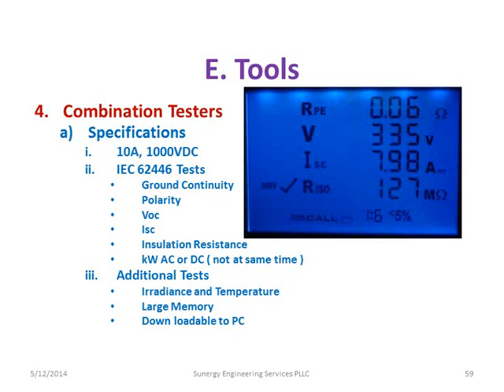So you can see in this is actually the unit right here, and what it looks like when it's live. RPE is the protective earth. That's what they call it in Europe. It's the resistance of protective earth, and it says what the ohms were. And of course, you want a pretty low number on that one. And usually, there's no limit on it based on the IEC, but usually I look at the size wires that you're using and the number of connections you have, and you can kind of estimate what the resistance in that wire should be. And as long as you're close to that number, then things are looking pretty good.